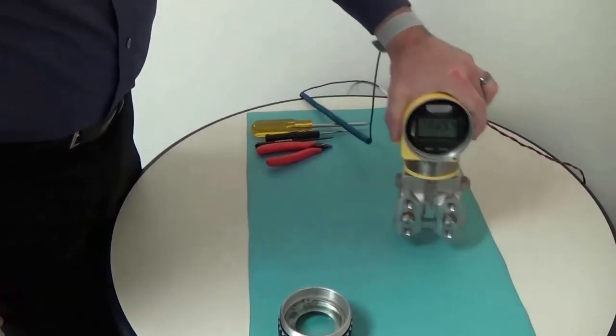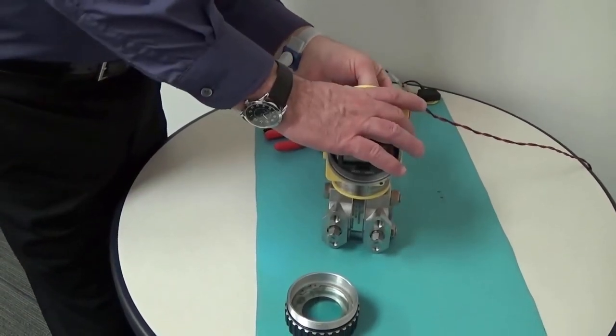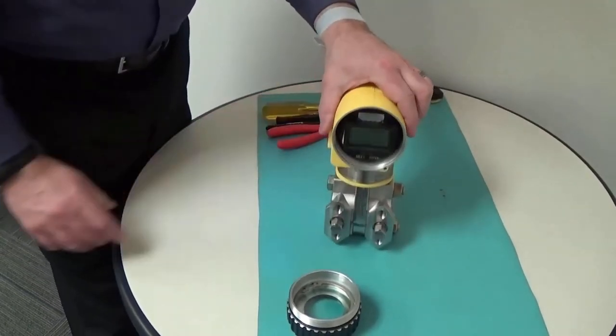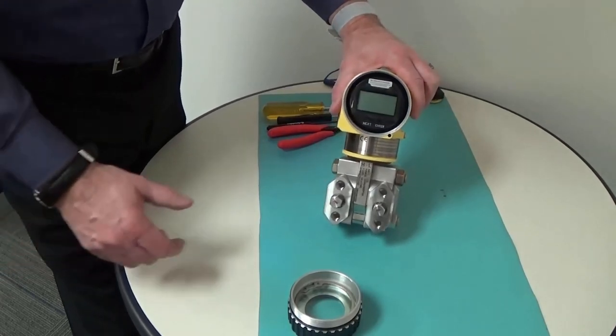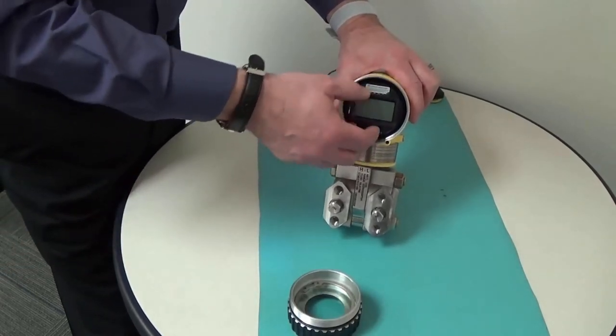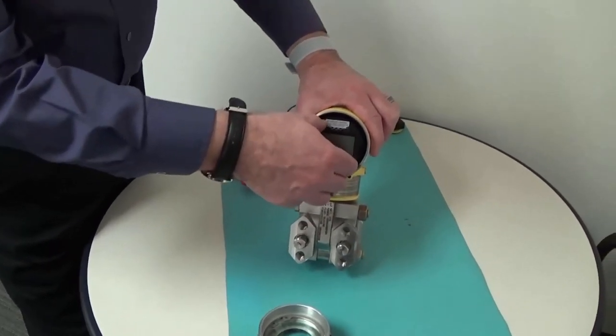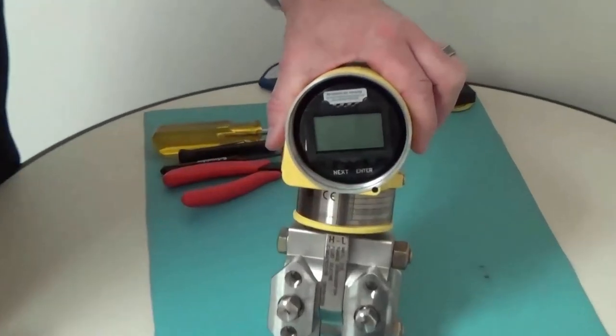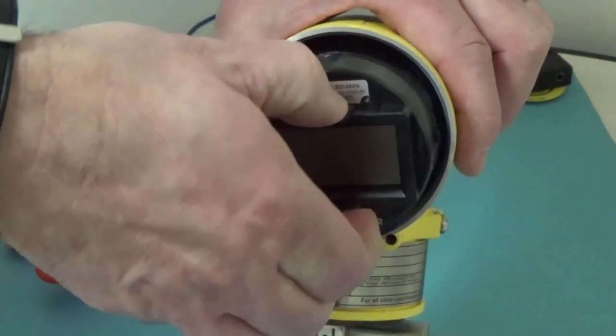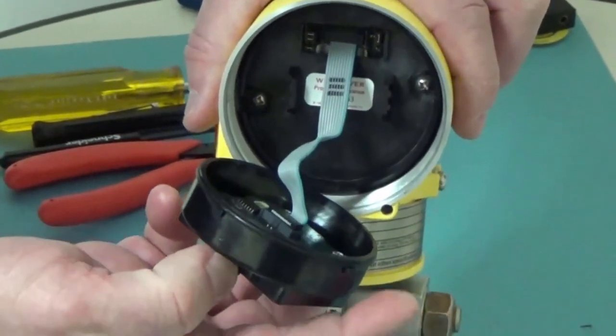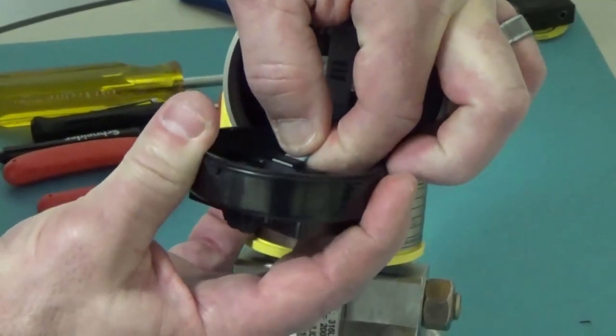The first step is to power down the transmitter in this particular case. I'll just remove the power and then the way to get into the unit to gain access to where the battery is is to remove the display. That can be done by just rotating the display slightly in the counterclockwise direction. There is a ribbon cable that's attached to it and so we can gently unplug the ribbon cable from the back of the display.